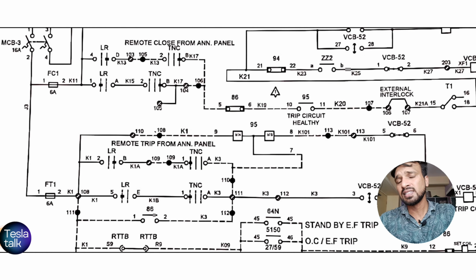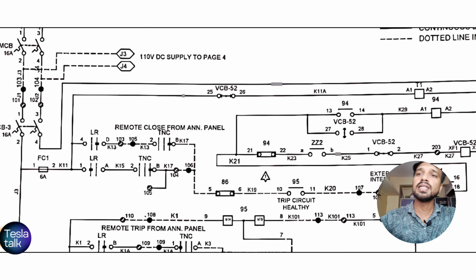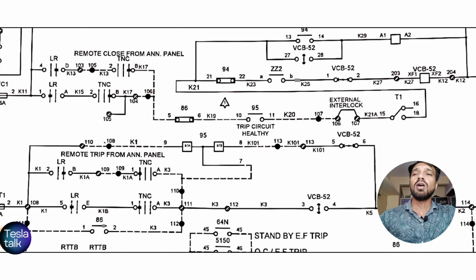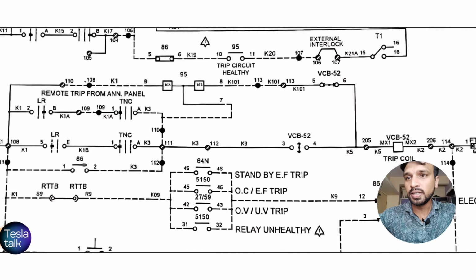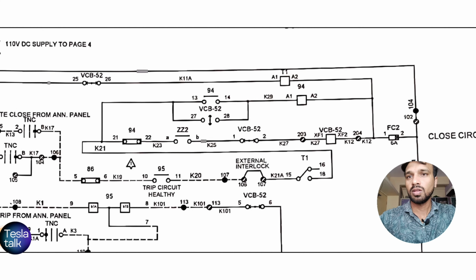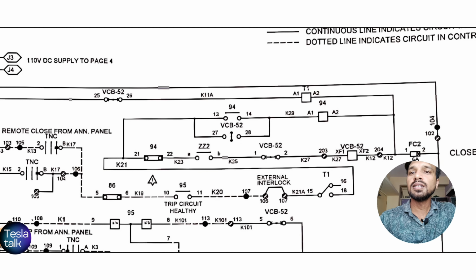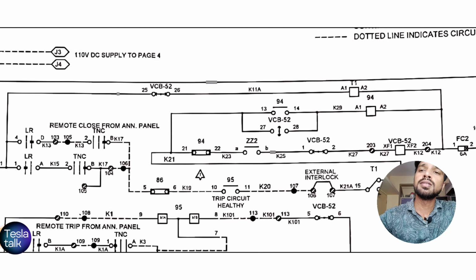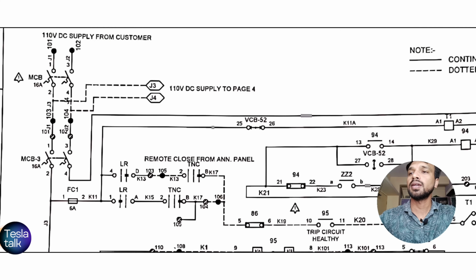Then this is the same circuit as we saw in the first schematic of the circuit breaker, but the only difference is that there are several relays used here, and there is a timer, and the 95 trip circuit healthy contact is externally used here.